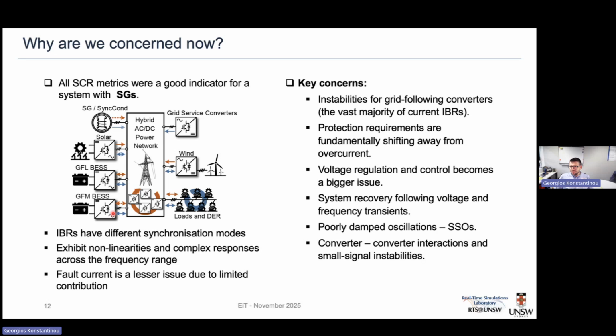This creates concerns we mentioned. We have to worry about instabilities that appear with a lot of grid-following converters, which are the vast majority of large and small scale systems connected in our network today, if we're using overcurrent for protection from things downstream of a feeder, for example. Since we're current limited, protection requirements fundamentally shift away from overcurrent because we can no longer supply very high fault currents quickly.